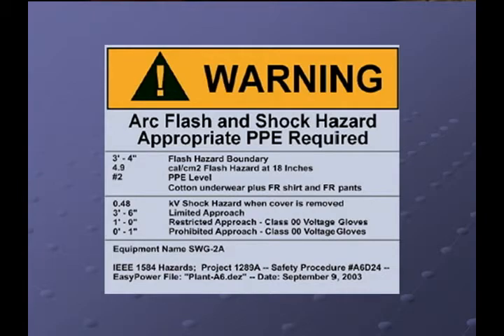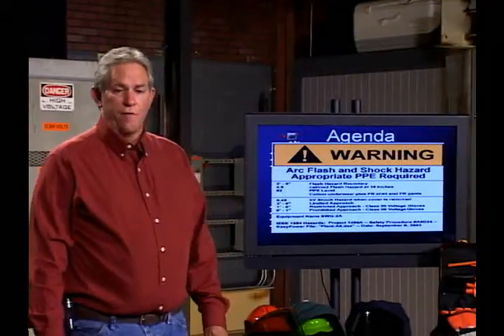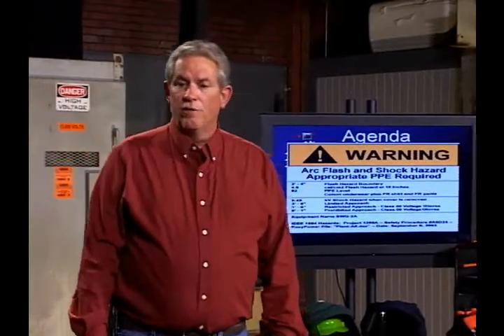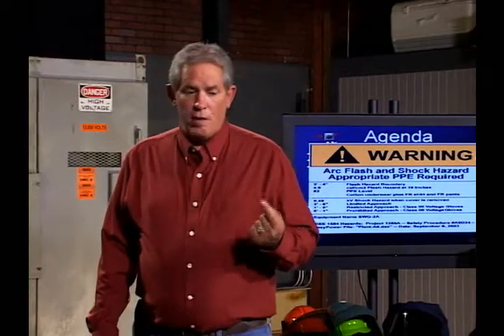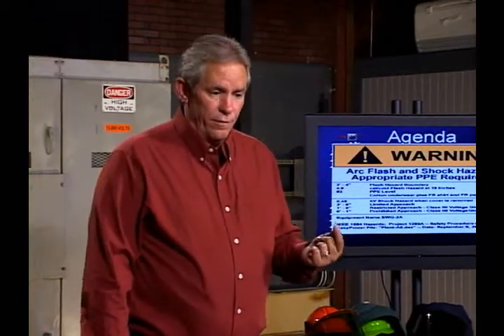The next section talks about the voltage level. Here it's 0.48 kV or 480 volts. Now we must avoid shock. And I hope you guys understand that there are actually 3 hazards. Number 1 is shock, number 2 is the arc, and number 3 is the blast. The shock always comes first. Let me repeat that again. The shock always comes first. You can be burnt to a crisp and still live.